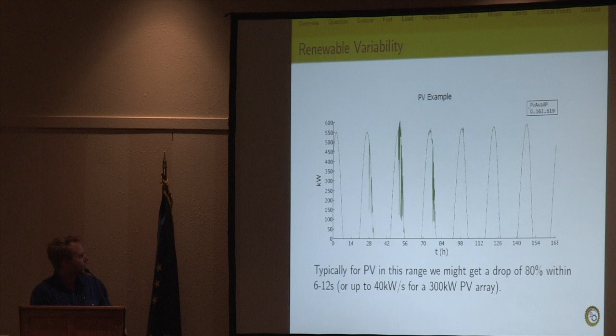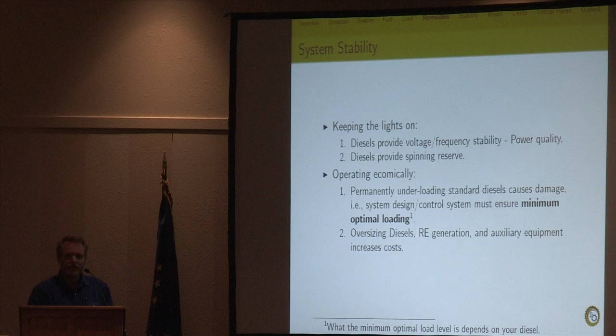Okay. So the diesels generally provide the stability in the system. They provide the spinning reserve. And to operate them economically, you don't generally want to permanently underload them. So you also have to make sure that you don't have too much renewable energy in the system, because your diesels still have to run in some form of a very lowly loaded mode. There are approaches to push the load lower on the diesels without damage, but in general we're looking at 20 to 30% loading, and that's what we used for the study here. If you oversize either your diesels or your renewable resource, you're increasing your cost, and you'll have a harder time running economically.